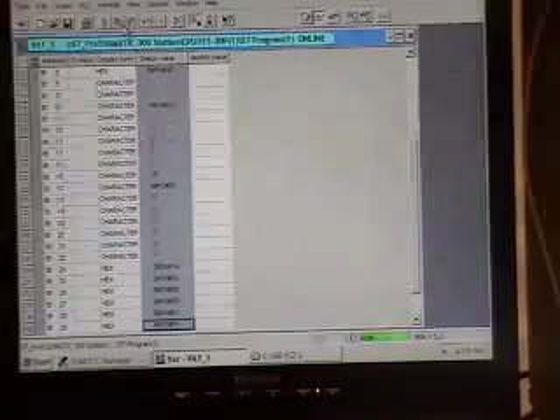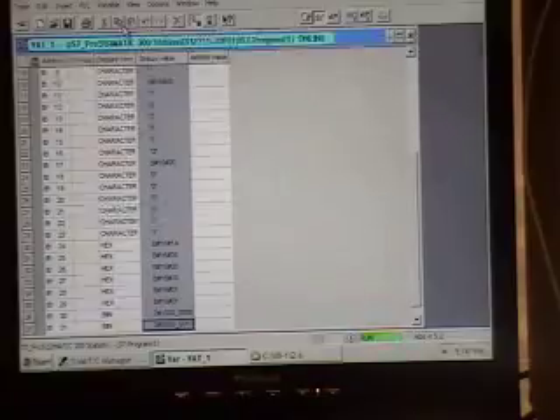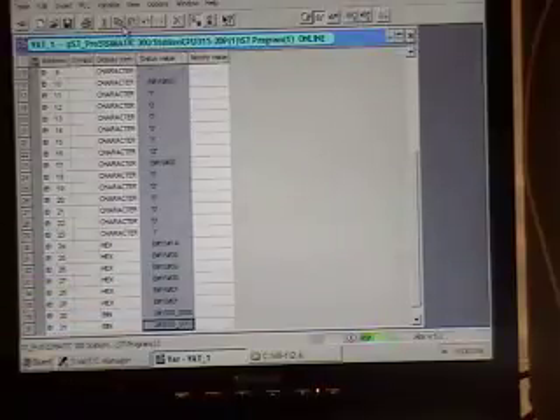And we have other bytes, other bits of information where we have troubleshooting information. Whether the flow is on or off, whether one of the pressure switches is open or closed, whether the network fault light is on, whether we lost communication with the network, whether we lost communication with the analyzer, and which valves are open or closed, since we have read back on this box, so we can tell which valve is open or closed, and you can see it here. So you get other troubleshooting or other tidbits of information that you cannot get if you just have computer override.